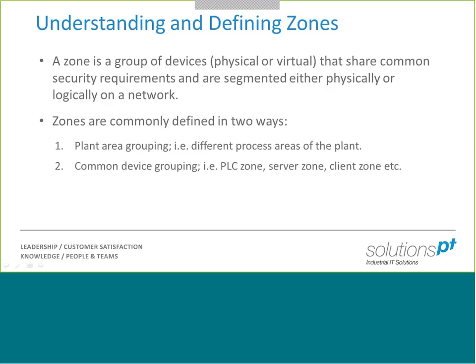So what I mean by that is if we only had a small handful of PLCs, servers, and workstations, for example, we may define a zone for each one of those. So a zone for our PLCs, a zone for our servers, a zone for our clients. Now, as I say, there's no straight answer to this question. It is the hardest part about defining the zones and understanding them. So it has to be approached on a case-by-case basis, but these are just two starting points for people to look at when defining them.